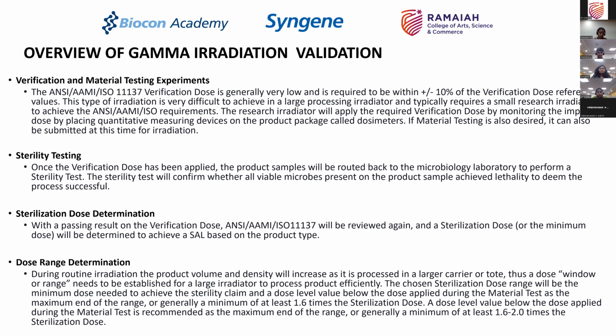Sterility testing. Once the verification dose has been applied, the product samples will be routed back to the microbiology lab to perform the sterility test. The sterility test will confirm whether all viable microbes present on the product have achieved lethality to deem the process successful. So it is a no-brainer that you are doing the chemical analysis. The second one is to ensure that the dosage is right, and the third one is primarily the sterility testing, because the whole purpose of doing gamma irradiation is to achieve sterility.